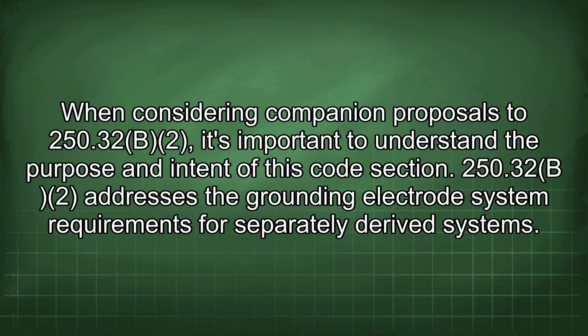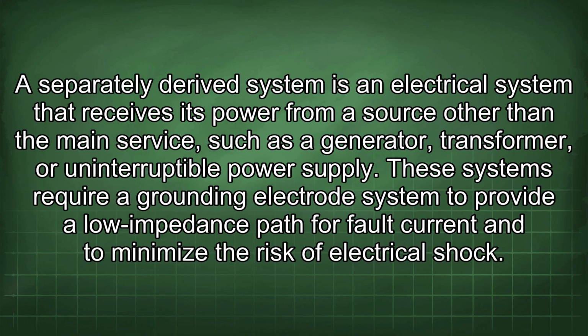When considering companion proposals to 250.32(B)(2), it's important to understand the purpose and intent of this code section. 250.32(B)(2) addresses the grounding electrode system requirements for separately derived systems. A separately derived system is an electrical system that receives its power from a source other than the main service, such as a generator, transformer, or uninterruptible power supply. These systems require a grounding electrode system to provide a low impedance path for fault current and to minimize the risk of electrical shock.